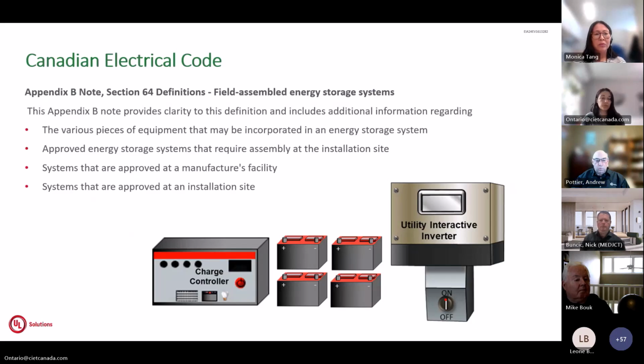There were some changes to definitions, and what you're seeing here is an Appendix B note, which is an informative section of the Canadian Electrical Code. This particular note speaks about field assembled energy storage systems. An energy storage system could comprise multiple pieces of equipment, including batteries, protection, control, power conversion, charge control, and fire detection, as mentioned in the previous presentation. This definition also applies to systems approved at a manufacturer's facility prior to field assembly, and to field assembled systems that require approval in the field.